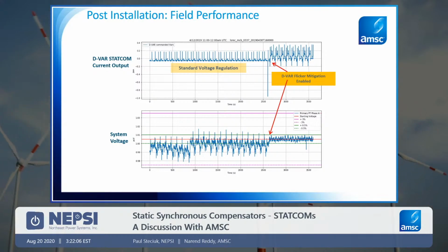It's a lot more relaxed, and the voltage variations, while they are still maintained within the requirements of the DVAR system between 0.98 and 1.02, the range that it's required to be maintained. It's doing that, but it's still relaxed a fair bit. But when the system switches over to DVAR flicker mitigation mode, well, now it's looking for actual flicker and trying to improve that.